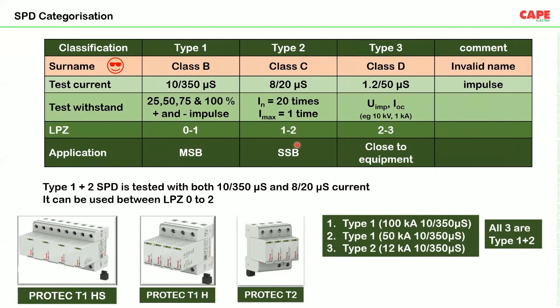part 2 of the seminar. But what you should understand is that these type 1 SPDs are also tested for type 2 parameters. So generally the manufacturers call this type 1 plus 2 SPD. By looking at type 1 plus 2 SPD, don't be more interested. It is a type 1 SPD, but tested for type 2 parameters as well. More than type 1, type 2, you must check how much current it can handle. For example, type 1 SPD 100 kiloampere, type 1 SPD 50 kiloampere, type 2 SPD 12 kiloampere. Sorry, it's not type 2, it's type 1. There is some small mistake in my presentation. So like this, you should always check the current parameters as well.